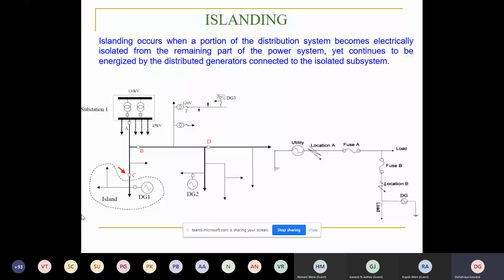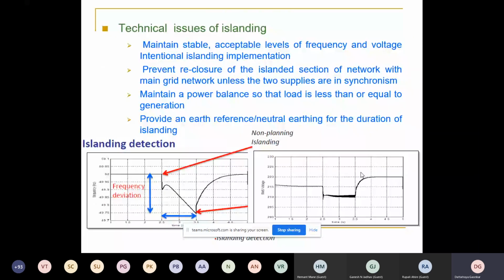If you have a photovoltaic system, why can't you feed your own things? We are doing this now with inverters. But these are all possible only with matching of load and generation. So what are those issues in islanding? The islanding issue is to maintain the voltage and the frequency.